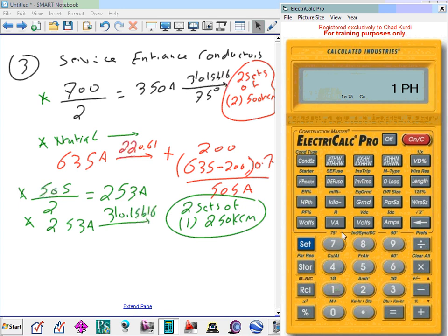Now, what's the amp of the overcurrent protection device that we have? 700, right? So the service is 700, and hit the amps. Regardless of the voltage, all you care about is 700 amps, right? How many sets do you want to parallel? Because I know 700, I can't carry it with one conductor. I need to parallel two. How many am I going to parallel? 2.